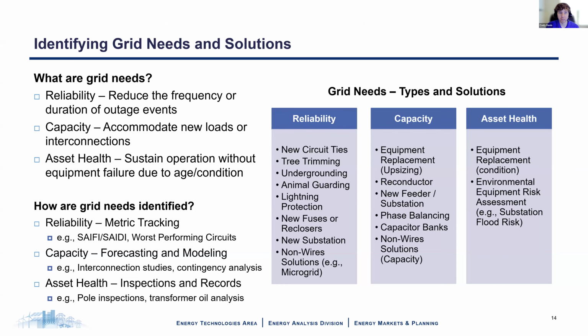Reliability reduces the frequency or duration of outages. Capacity is the ability to accommodate new loads or interconnections. And asset health is the ability to keep things running without equipment failing due to age and condition. So how do we identify grid needs for reliability? We're tracking metrics and outage data, things like SAIFI and SAIDI, which are metrics for tracking the frequency and duration of outages, either at the system level or on individual feeders. There are mechanisms like worst performing circuits that classify which circuits have the worst reliability, like the worst 5% of circuits for SAIFI.